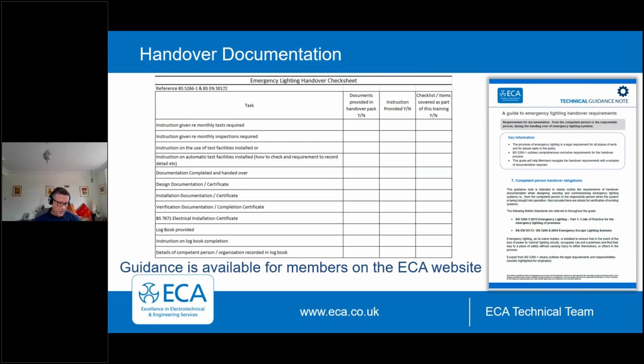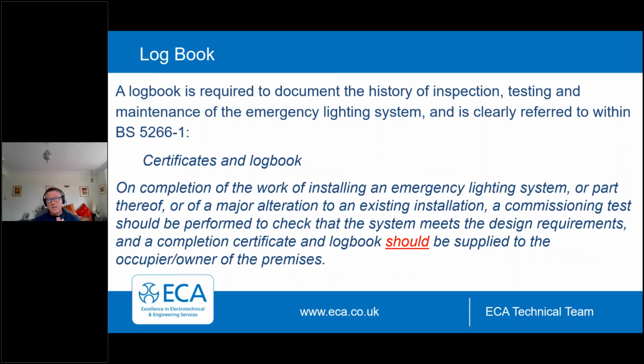Now, the logbook is quite a big one, because the logbook is required to contain a lot of detail, a lot of instruction, such as this. It is required to document the history of inspection, testing and maintenance. And it is clearly referred to in 5266 in this way.